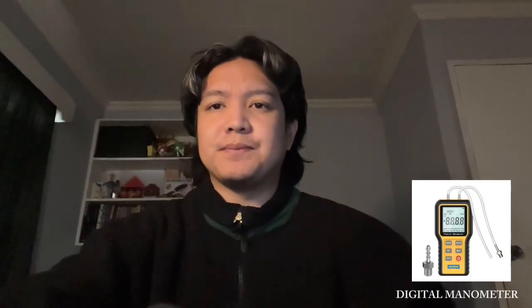So how does a digital manometer work? Unlike traditional manometers, digital manometers do not rely on a hydrostatic balance of fluids, water or mercury, in order to detect pressure. Rather, they come with a component known as a pressure transducer that converts the level of pressure observed into an electrical signal value. The value then can be recorded as the amount of pressure present. There are usually three types of electrical variables used by pressure transducers: resistive, capacitive, and inductive.